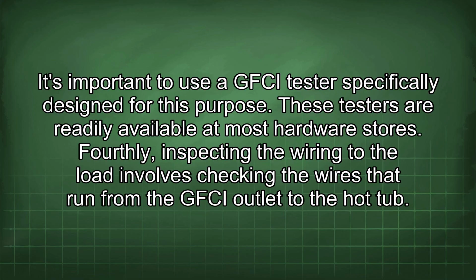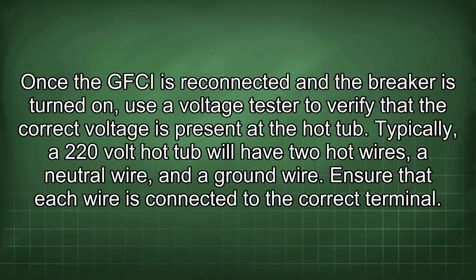Fourthly, inspecting the wiring to the load involves checking the wires that run from the GFCI outlet to the hot tub. Once the GFCI is reconnected and the breaker is turned on, use a voltage tester to verify that the correct voltage is present at the hot tub. Typically, a 220-volt hot tub will have two hot wires, a neutral wire, and a ground wire.